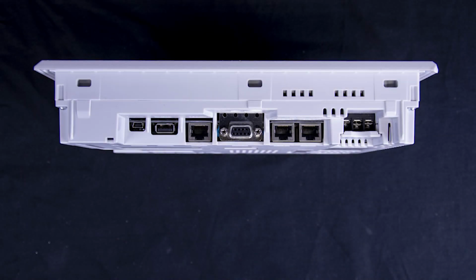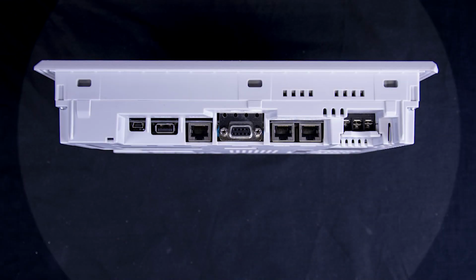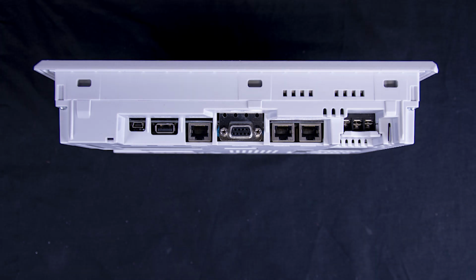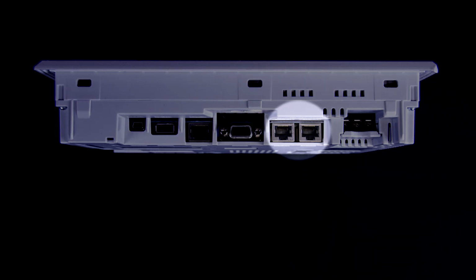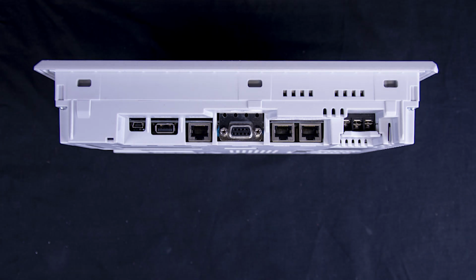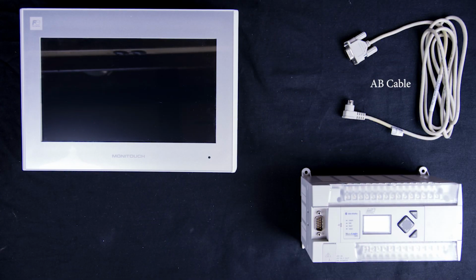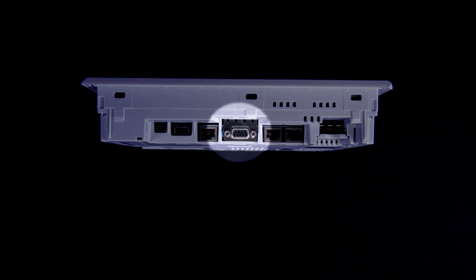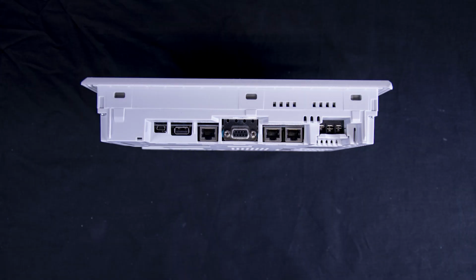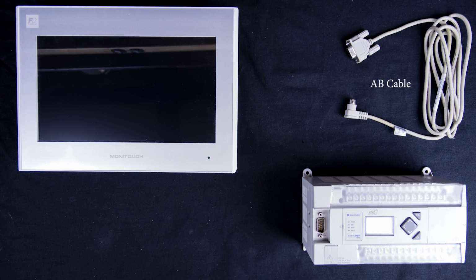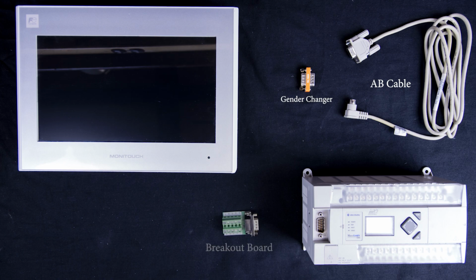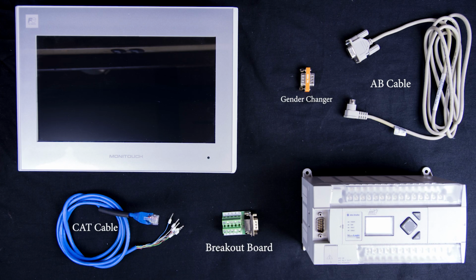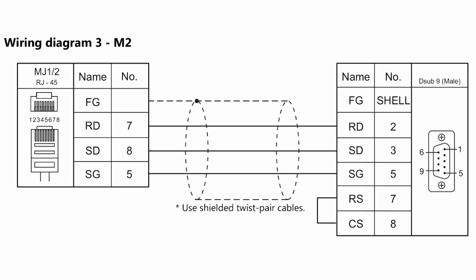First, hardware setup. For a serial setup, use either the V9's D-sub CN1 serial port or the RJ45-style MJ1 and MJ2 serial ports on the HMI. In both cases, Allen Bradley's serial cable is needed. The CN1 port is not available on 6 and 7-inch V9 models. For the CN1 port, a gender changer may be required. In the case of the MJ1 and MJ2 ports, a breakout board and twisted copper pair cable should be used. Follow wire diagram 3-M2 as noted in the connection manual.